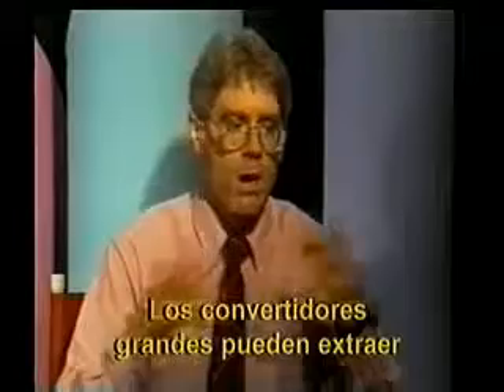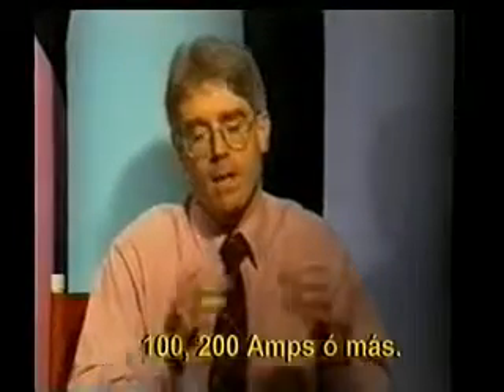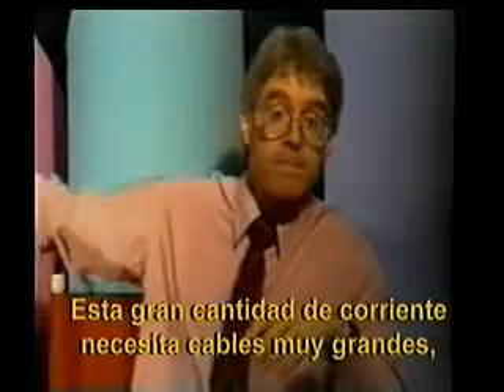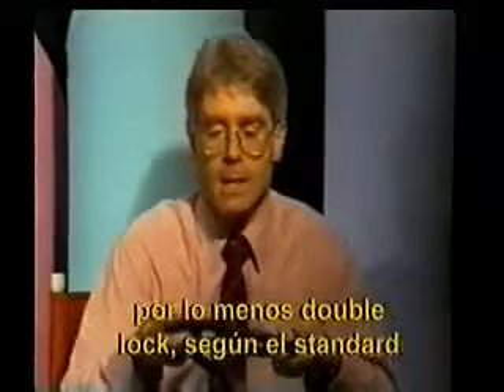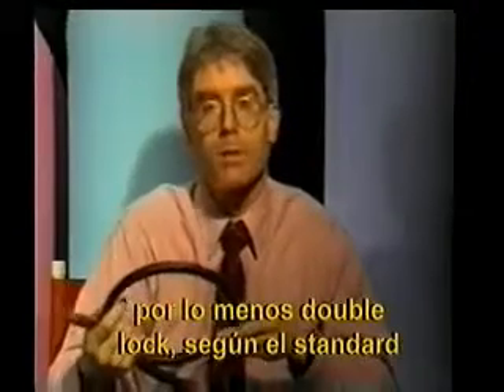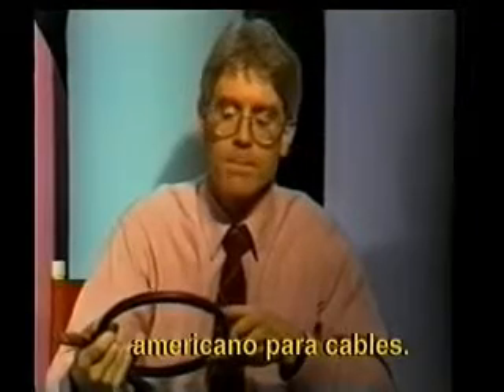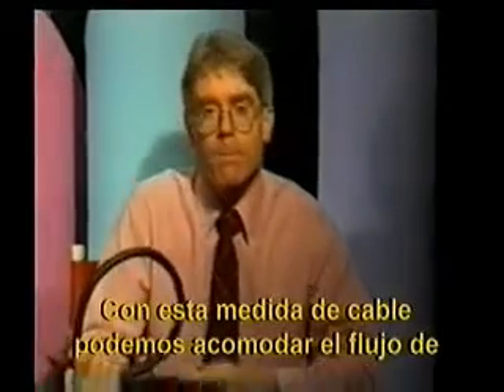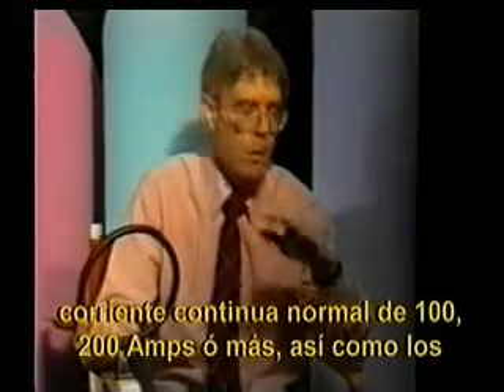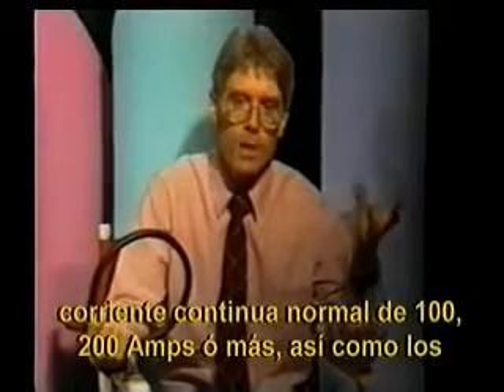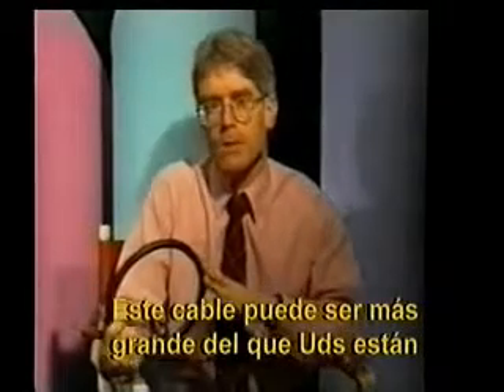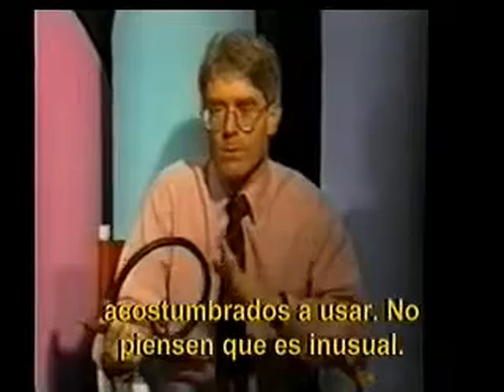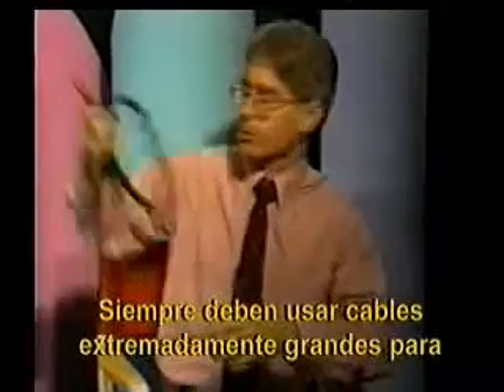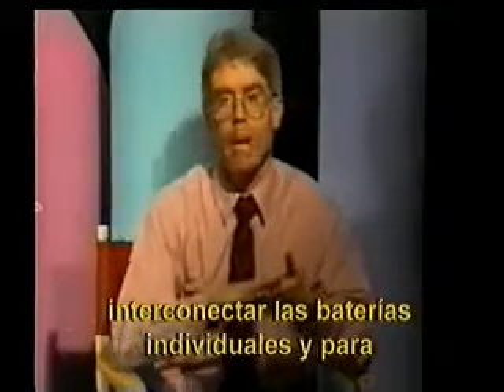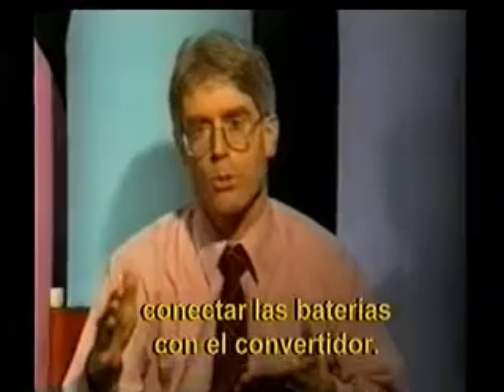Typically, large inverters can draw 100, 200 amps or more. This large amount of current needs to be accommodated by very large wire. Typically a wire that's sized to be at least double-aught, maybe 4-aught wire in American wire gauge standard. Using this size of wire, we can accommodate the normal continuous current flows of 100, 200 or more amps, and also accommodate the surge currents that are even higher than that. This size of wire might be larger than you're typically used to dealing with. Don't think that it's unusual. You should always use extremely large wire for interconnecting your individual batteries and for connecting your batteries to your inverters.